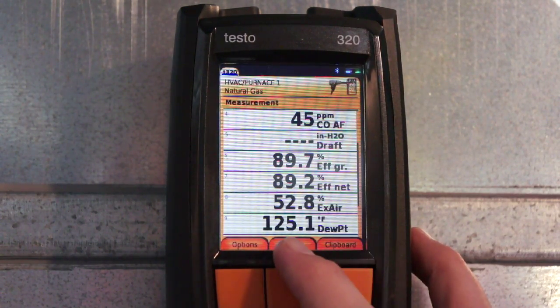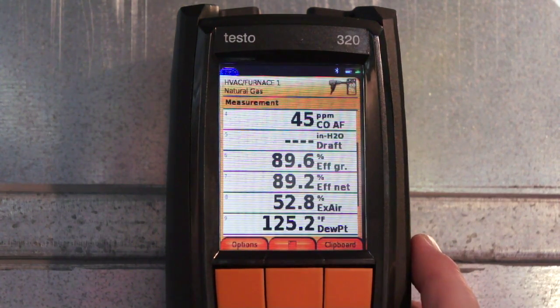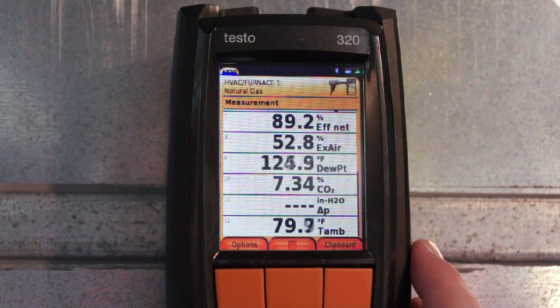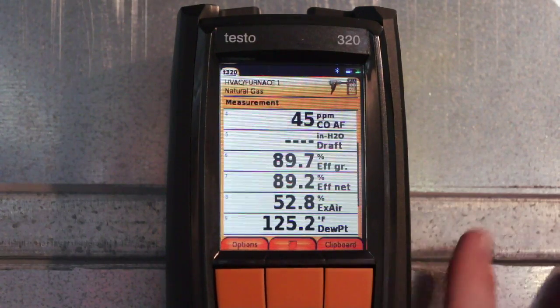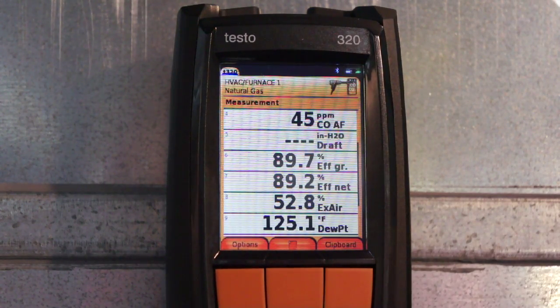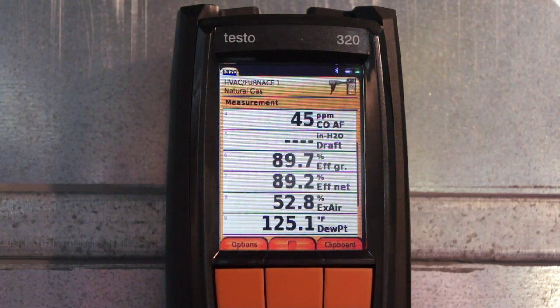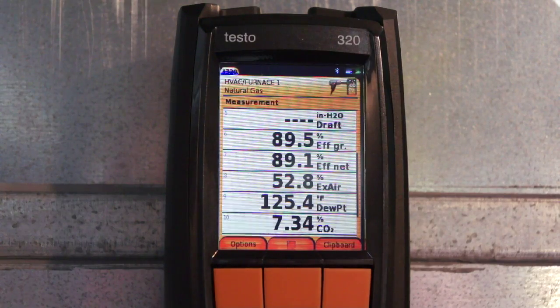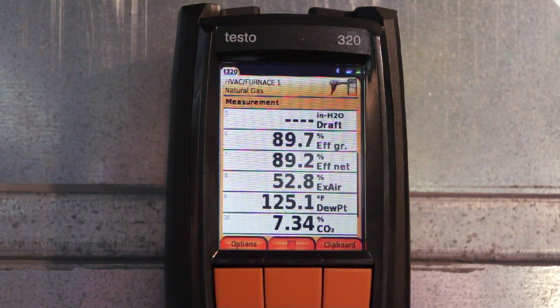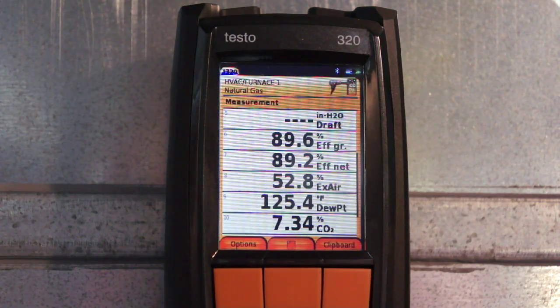Scroll down again, I can see the dew point of my flue gas. You can see it's 125 degrees. That should be exactly the same as my stack temperature. I'm going to scroll back up here for just a second. My stack temperature is 125.5. Scroll back down. My dew point temperature is 125.5, same as that. You can see it bouncing around right there. The reason the dew point temperature and the stack temperature are the same is because, again, I'm in the condensing mode. Scroll down again, I have CO2. If you're used to looking at CO2, 7.34% CO2 is pretty typical for this type of appliance.